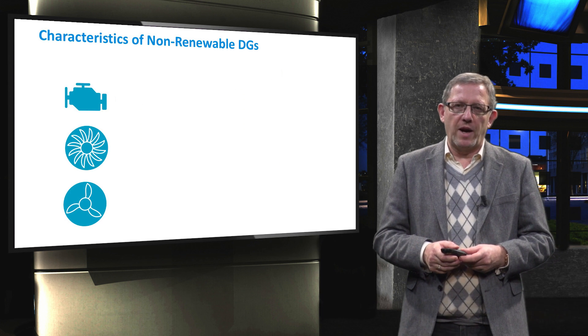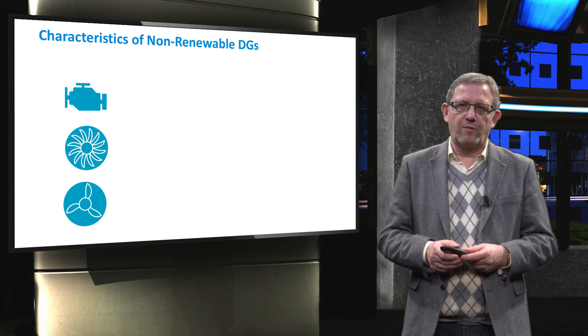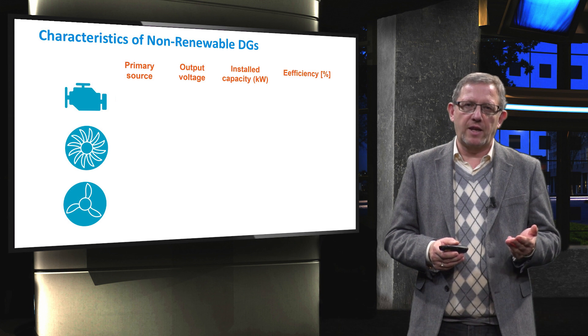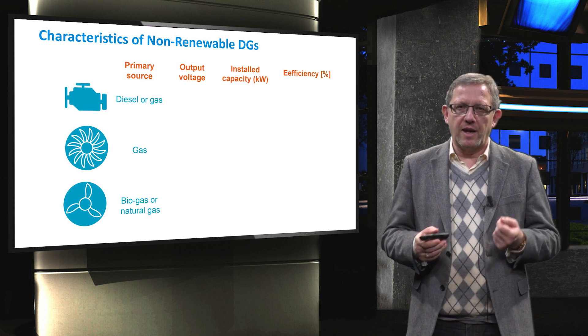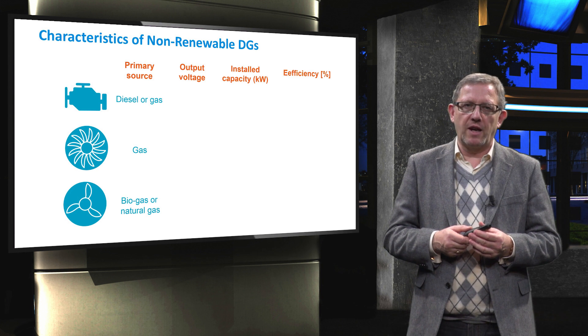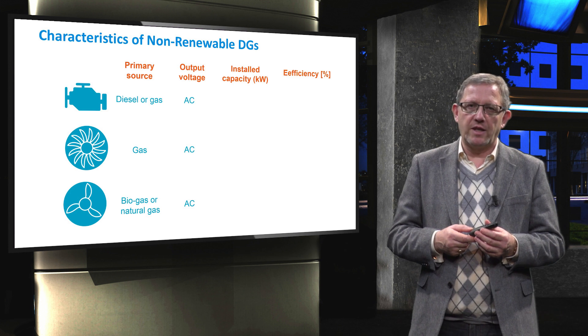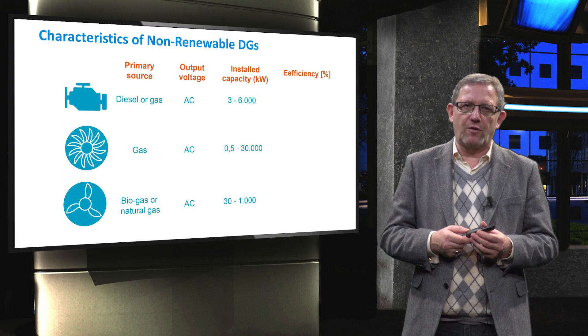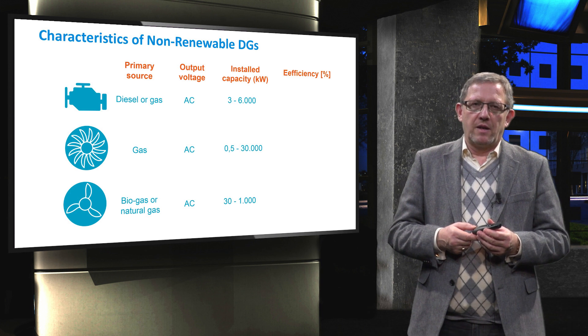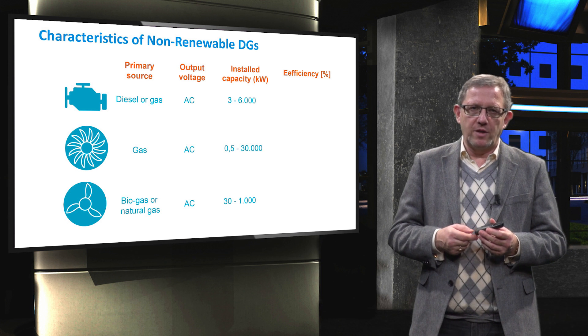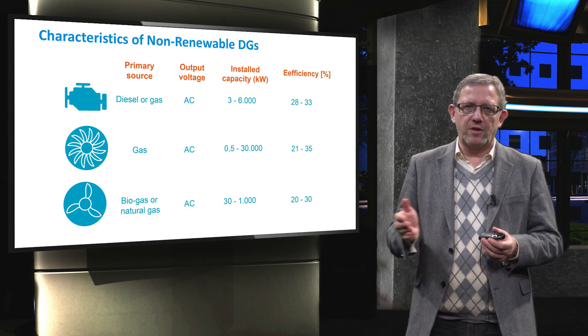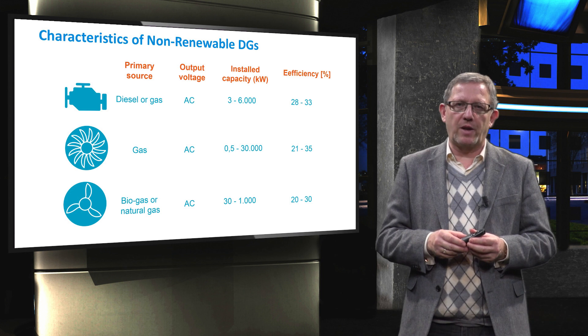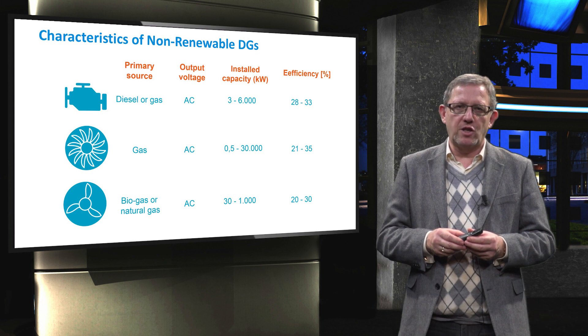In this slide, we compare the three previously introduced technologies in terms of primary source, output voltage, installed capacity, and electrical efficiency. Diesel and gas are the primary sources of reciprocating and gas engines. All three generators operate with an AC output voltage and could reach an installed capacity of 30 megawatt. Their electrical efficiency, which depends on the operating point, is approximately between 20 and 35 percent. Note that if gas turbines are used for combined heat and power applications, they may reach up to 80 percent efficiency.